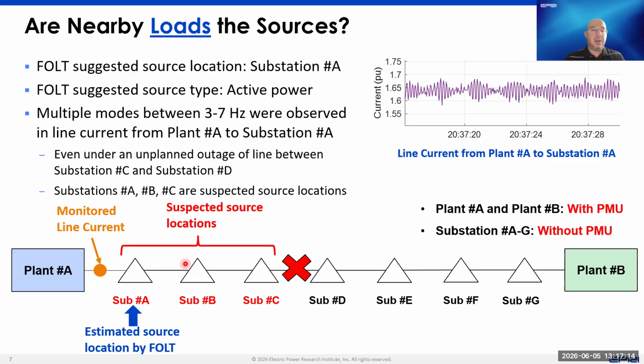Looking deeper into the topology of the system, we have a plant on the left-hand side. In this plant there was a PMU measuring the voltage and the current on the line connected to that substation. That substation is radially connected to other substations. On the right-hand side there is also another plant, which also has a PMU. Based on the analysis and all the PMU data that we used as input to the tool, we identified substation A as the candidate source for the oscillations.